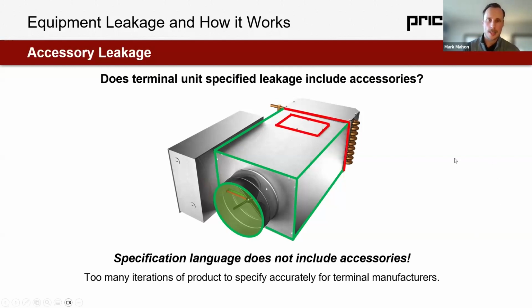But when we look at those transverse joints and when we look at access door seams, that is not included in specified language. And is that a problem? I would argue, yeah, it's a bit of a problem. But that is the way that product historically has been specified, the way that manufacturers build it. So I'm going to raise the kind of red flag to say it's something to consider. It's something that we're working on managing and offering a better method of doing this to the industry. And I'll speak a little bit to that too, but independent of manufacturer, you have to know an access door is not included in their specified language.